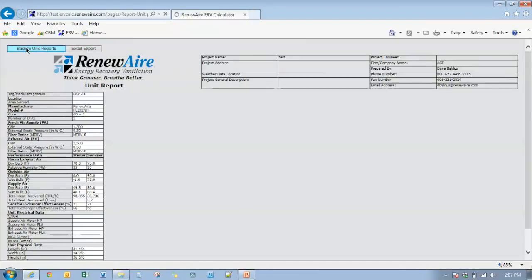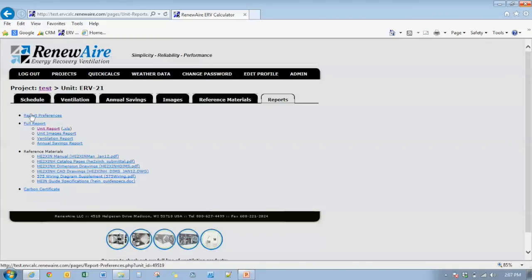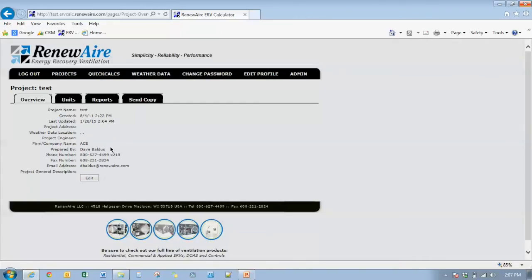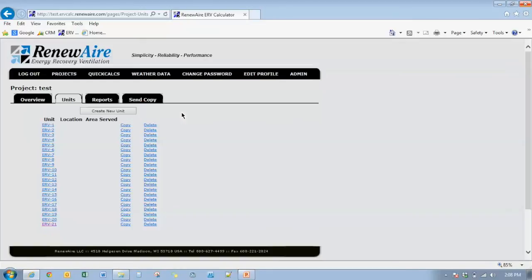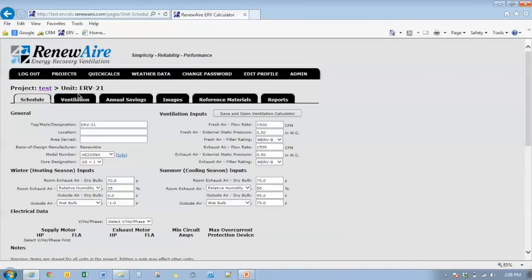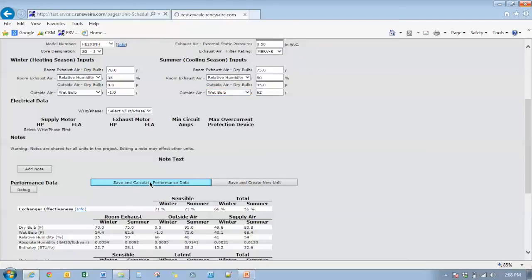Go back to our unit reports. And we're going to go back to our unit selection. In addition to the changes in the calculation process, we also incorporated a change for calculating recovery effectiveness in very arid conditions. Very dry conditions such as in the southwest United States. We changed the outside wet bulb condition down to 62 degrees. And do save and calculate.